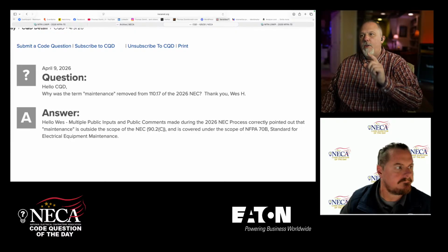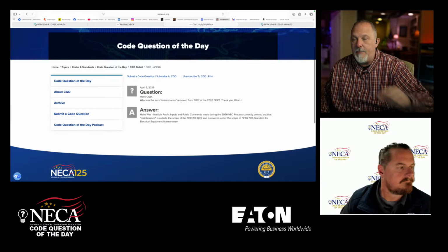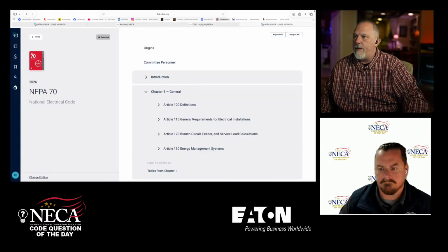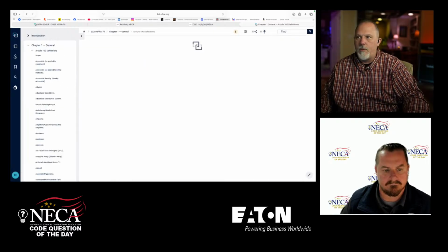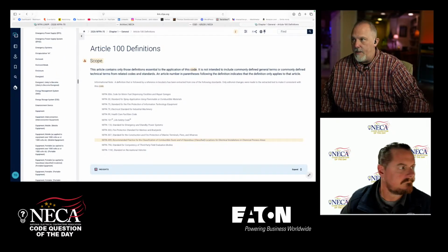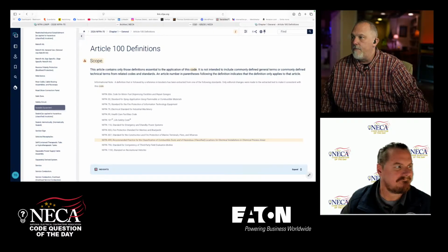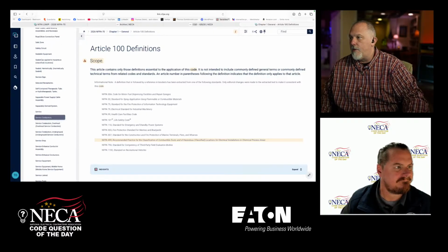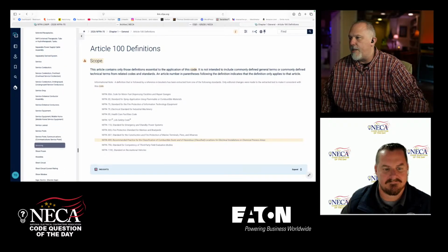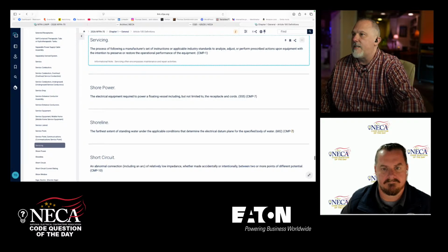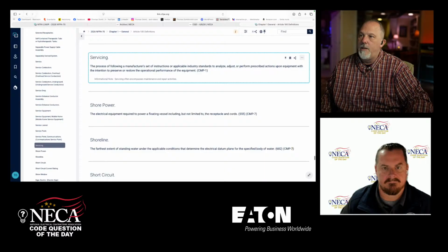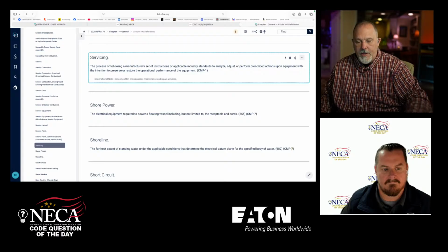Why was the term maintenance removed from 110.17 of the 2026 code? If you look at the panel statement and the substantiation, if I go to NFPA 70, the 2026, and go to Article 100, and we look up servicing as a defined term, I always say the terms servicing, service drop, service lateral. The defined terms is the gateway to the National Electrical Code. What servicing says is the process of following a manufacturer's set of instructions or applicable industry standards to analyze, adjust, or perform prescribed actions upon equipment, with the intention to preserve or restore the operational performance.